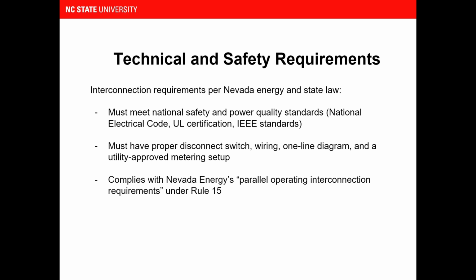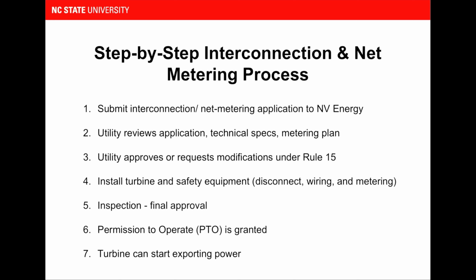All of this must align with the requirements laid out in NV Energy's Rule 15, which I mentioned earlier, which spells out how customer systems must operate when running in parallel with the grid. If the system meets these national and state standards, it significantly increases the likelihood of utility approval. Now I'll walk through the interconnection process step by step.